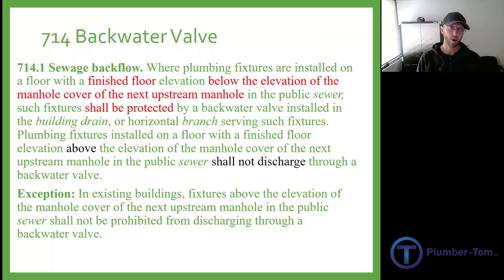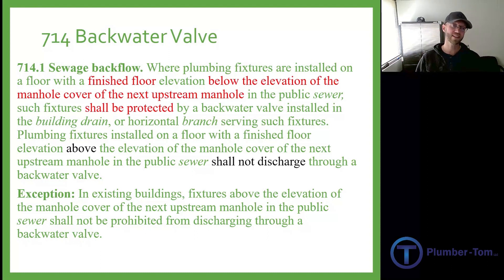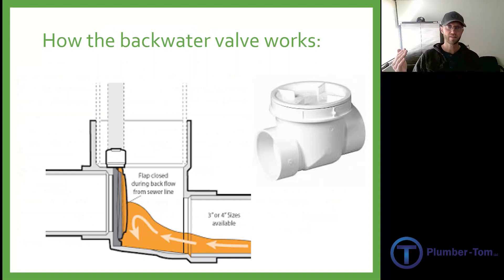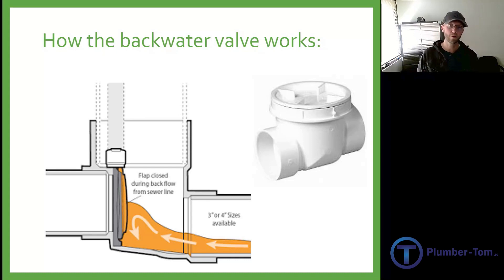Section 714 covers backwater valves. 714.1 says where plumbing fixtures are installed on a floor with a finished floor elevation below the elevation of the manhole cover of the next upstream manhole in the public sewer, such fixtures shall be protected by a backwater valve installed in the building drain or the horizontal branch serving those fixtures. A backwater valve has a simple flap inside that allows fluids to flow in the correct direction — from the drains out to the sewer — but if the sewer backs up the flap closes and keeps the house from filling with sewer. Some people love these because they've saved their basements from massive sewage floods; some hate them because they can cause clogs and blockages that may also flood the basement.